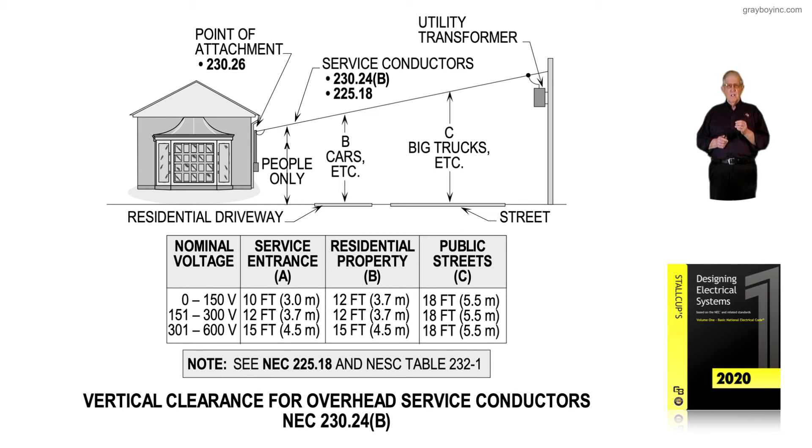Figure 6-14 deals with vertical clearance for overhead service conductors in conjunction with NEC 230.24B. If feeders are crossing and attaching, you would need to look at NEC 225.18 for those rules. In the National Electrical Safety Code, review Table 232-1 and the notes below it to satisfy both codes. If you cross streets or railroads, you'll need to work with the relevant street commissions and the railroad commission for anything crossing their right-of-way.